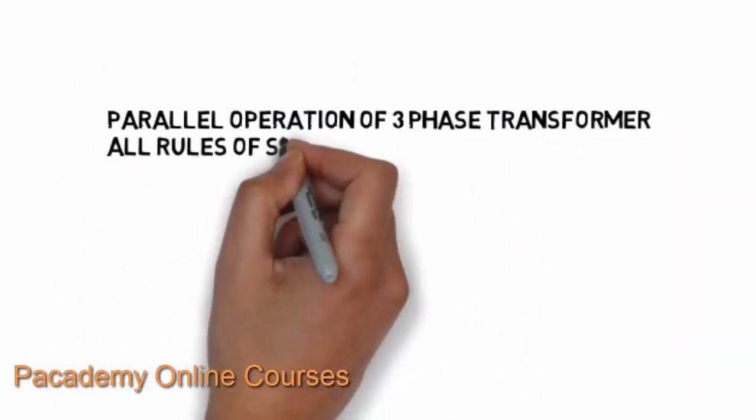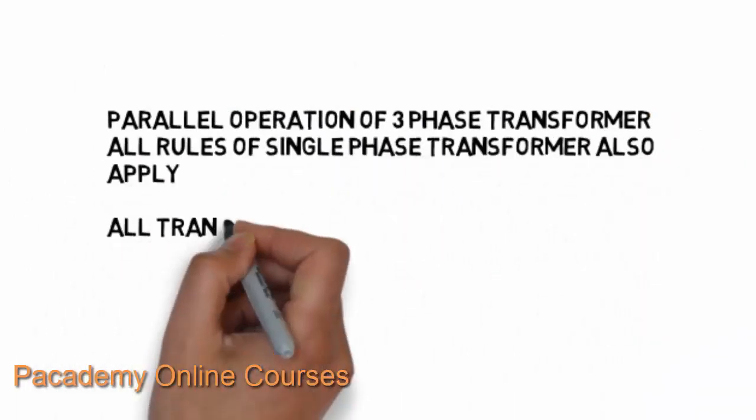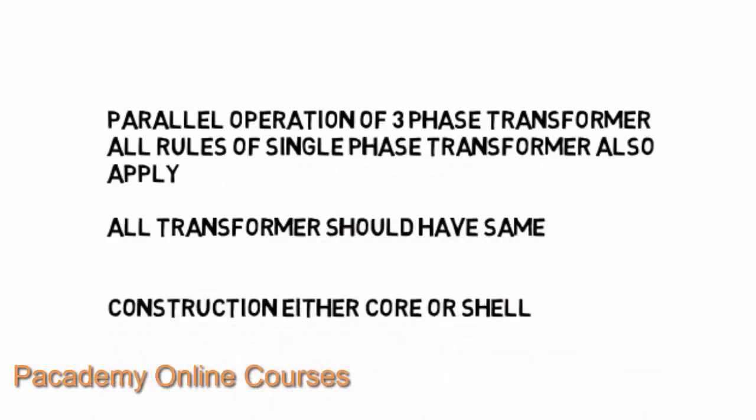For the parallel operation of three-phase transformers, the same rules that apply to single-phase transformers also apply. Additionally, all transformers should have similar construction — that is, if two units are used, both should be core-type transformers or both should be shell-type transformers.